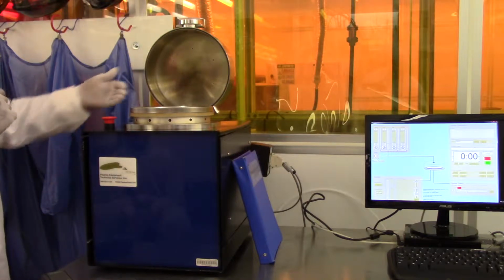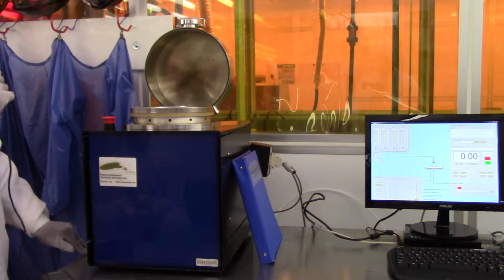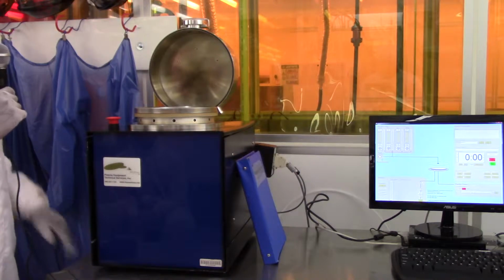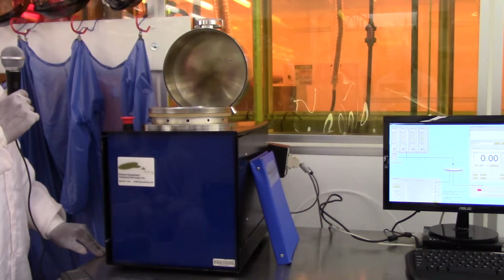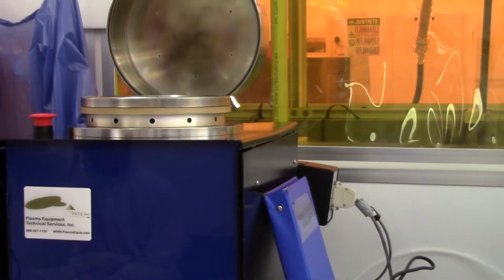Open the lid. Now you can really hear the nitrogen vent. You see that we have a 12-inch platen. It can typically hold three 4-inch wafers, several dies, or of course one 6-inch wafer. And this is our free-for-all chamber, so pretty much every material is allowed in here.